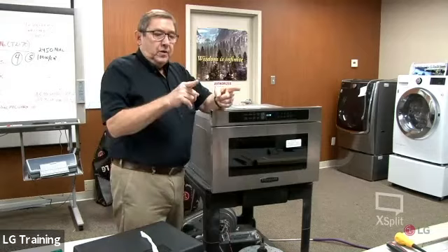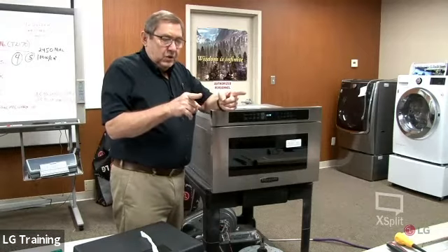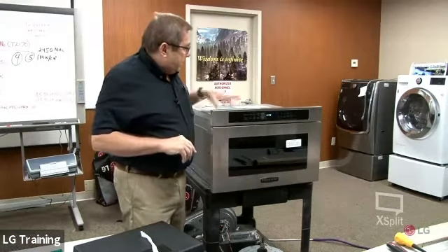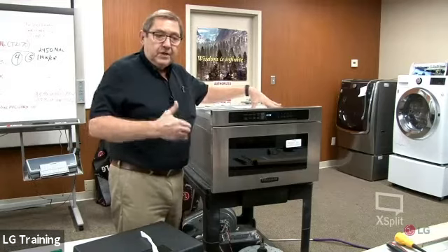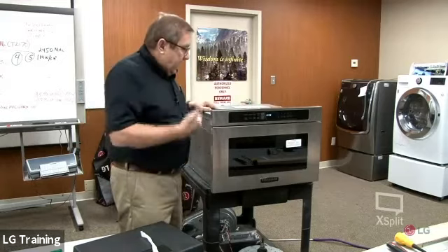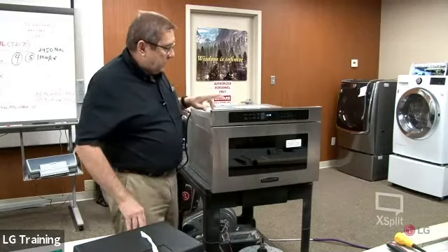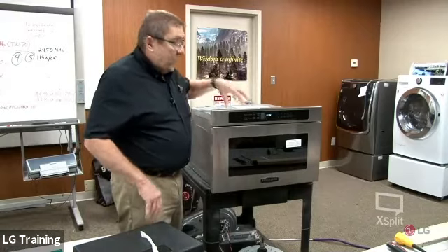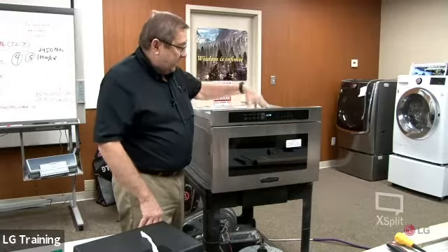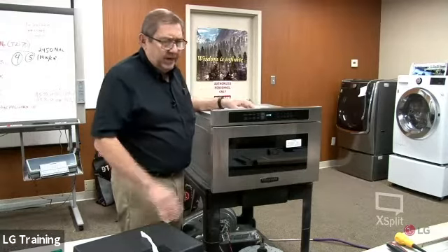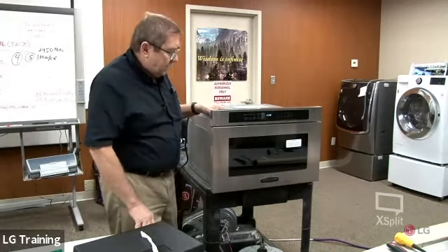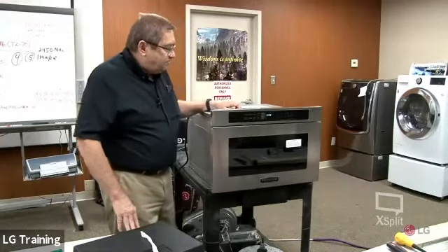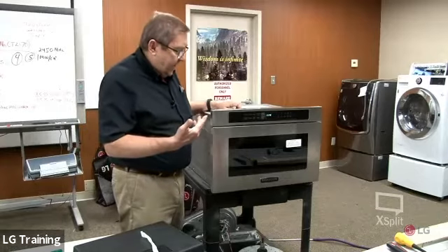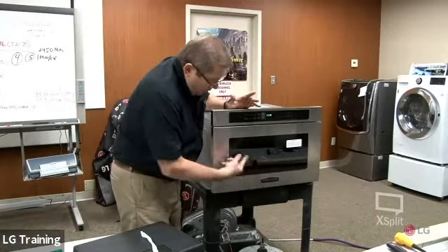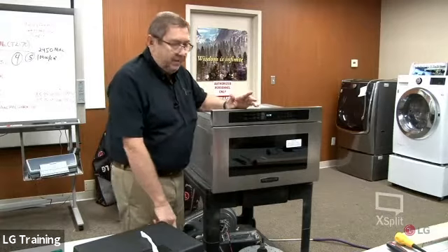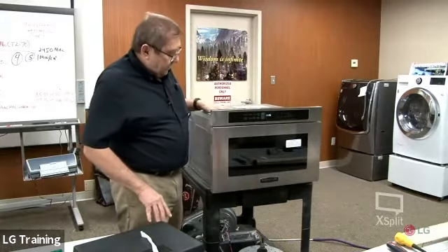Now there's also another little board down there, and they call that a switch power supply. Basically what they're doing is taking line voltage and converting it to 24 volts DC. They use that voltage for a couple things - we've got relays that activate, they claim it's about 26 volts, and when I was checking it I got somewhere between 24 and 26 volts. And the little motor for the door also runs off 24 volts DC.